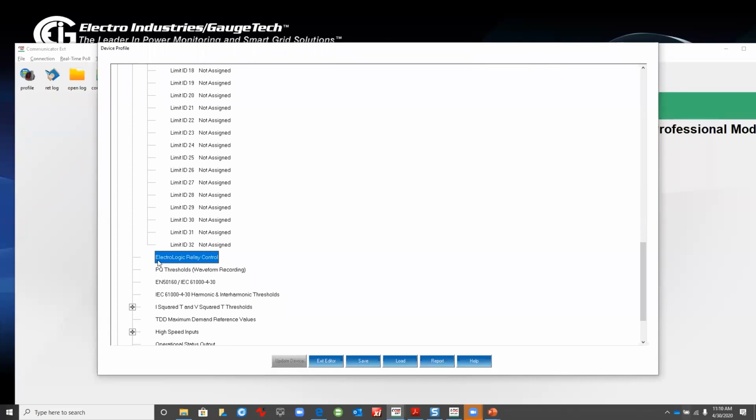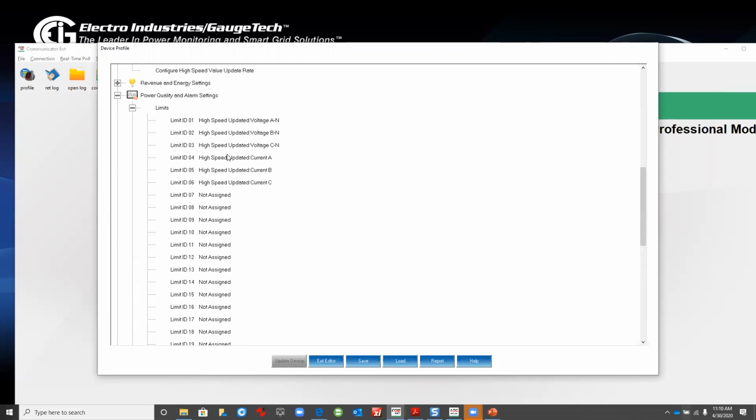Before I leave that section, I wanted to say that we set up the triggers to set up the alarms for each user, and we have to make sure that the CTPT is set up first. It's something that we cannot overlook prior to setting up the limits here, because it kicks off from that information.